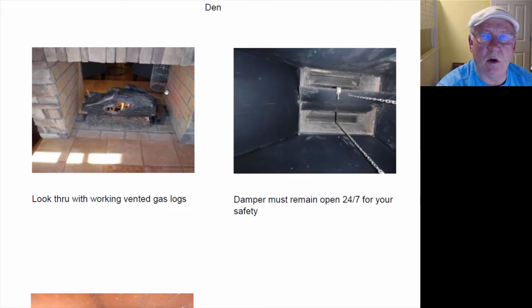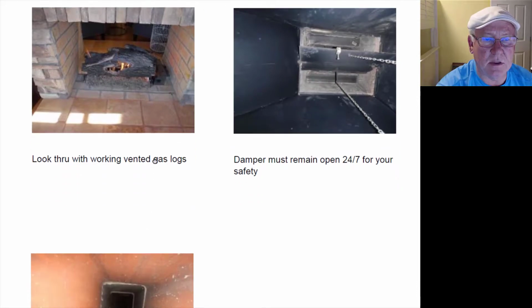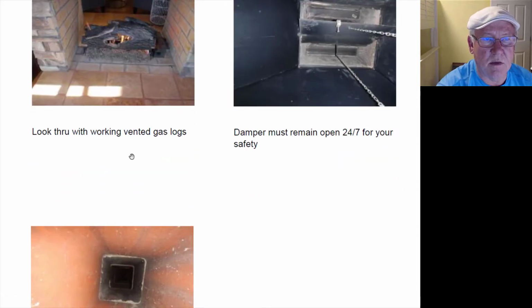Air is pouring in from both sides. Basically what happens is it overruns the flue system and can come back into the room. We tested on both sides and there was no carbon monoxide coming in, but absolutely if you tried to burn wood in here, you would smoke up your house. So gas logs, these gas logs need to stay in place. Today they were operating correctly. I can't account for what happened in the future, but today they were operating correctly.